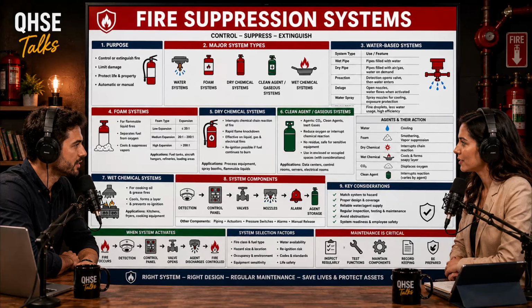What's the other type? The fusible link. It uses two small pieces of metal held together by a special solder alloy engineered to melt at a highly specific temperature. When it melts, the plug falls away. But the key here is that the heat physically breaks the mechanism on that one specific sprinkler head. Exactly. The fire alarm down the hall has absolutely no physical connection to the sprinkler head.